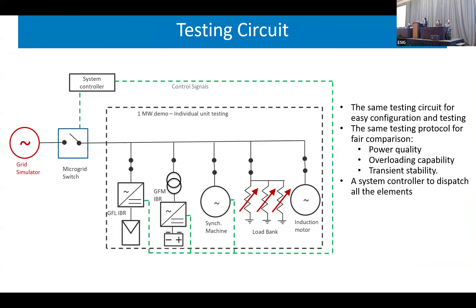In the next slide I want to show you the testing circuit. Because we are doing standard benchmark testing and comparing performance between inverters, we need to use the same circuit. This diagram shows the common circuit used to test each individual inverter. We have a grid simulator, a microgrid switch, the grid-forming inverter in parallel, a synchronous machine, a resistive or linear load, and an induction motor to provide inrush current to test the grid-forming inverter capabilities.